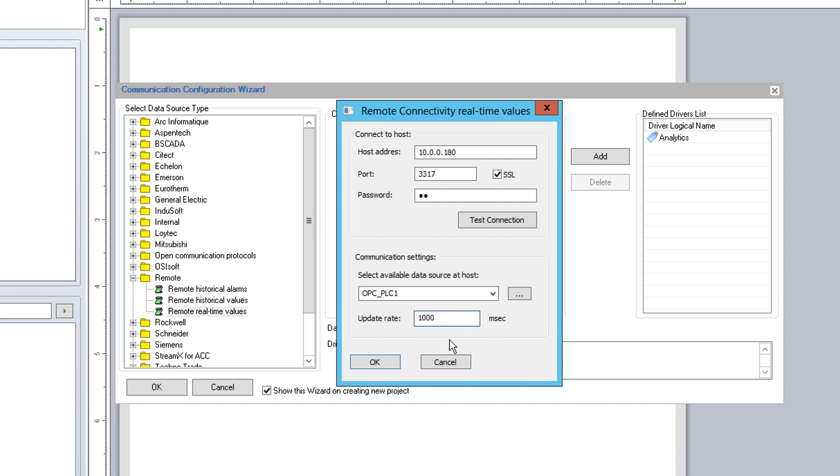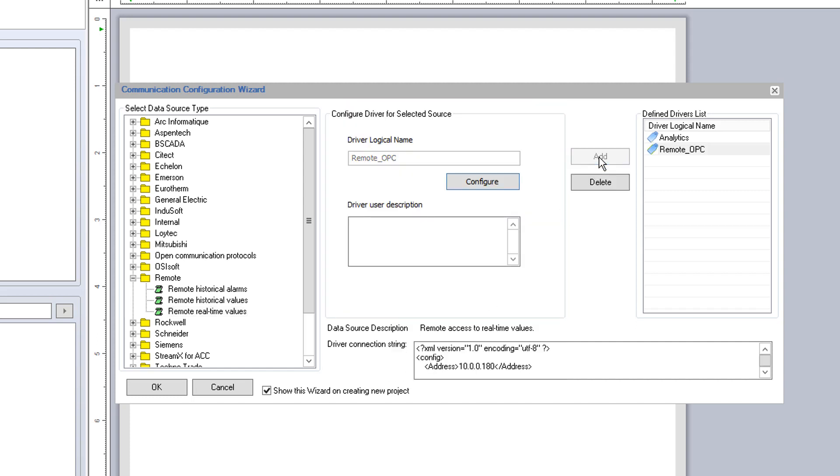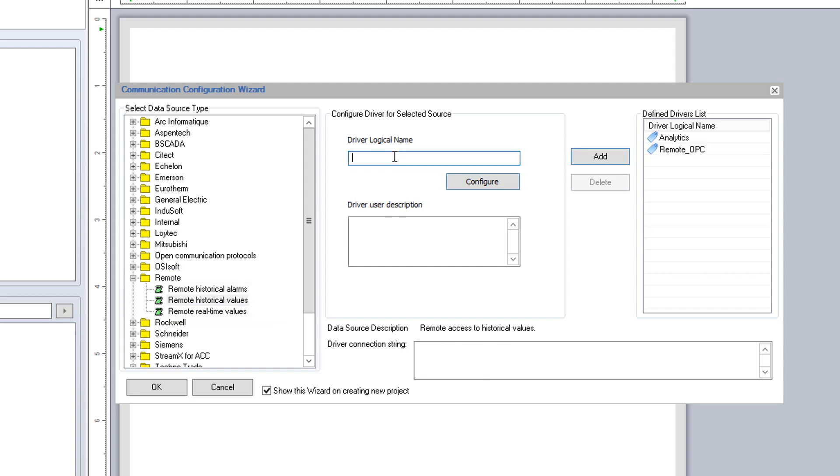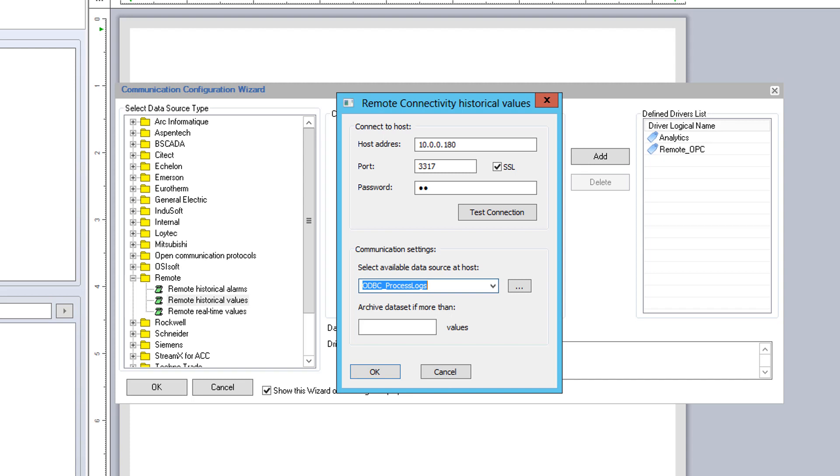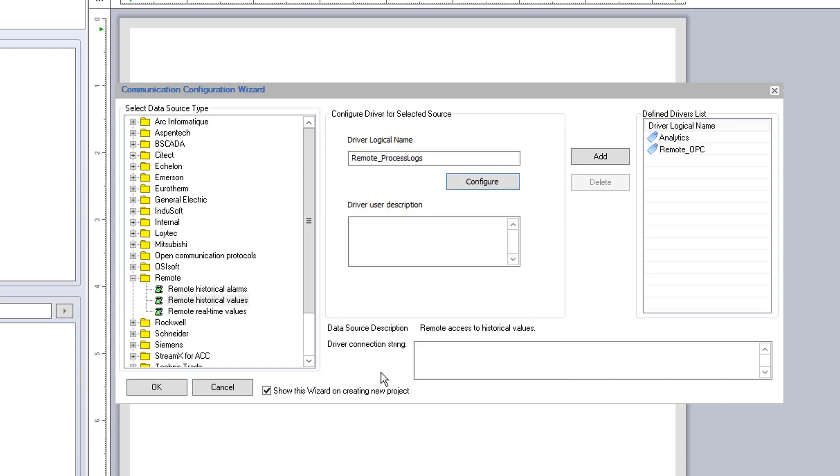Once done, I will add it to the project and then also quickly set up a connection to the remote historical values driver. After picking the remote driver, I can configure the driver to archive the dataset if more than X number of values are returned for a report query. This setting allows the remote connector to create a compression package of X number of data points or values from the historical archive at the host side and send that compressed package of data to the remote driver on the DreamReport side, where it is uncompressed and then reported on.